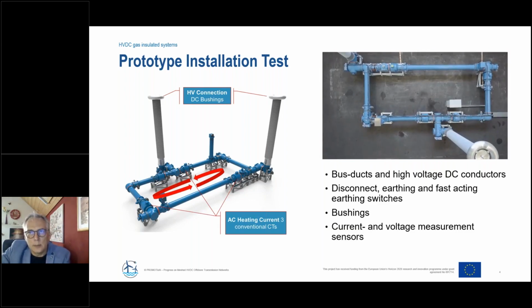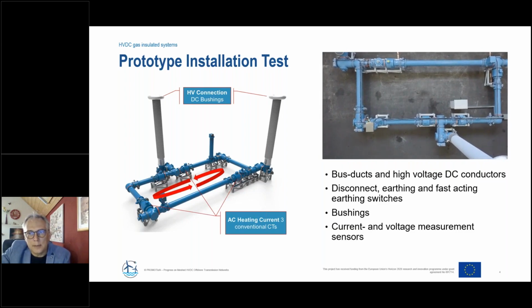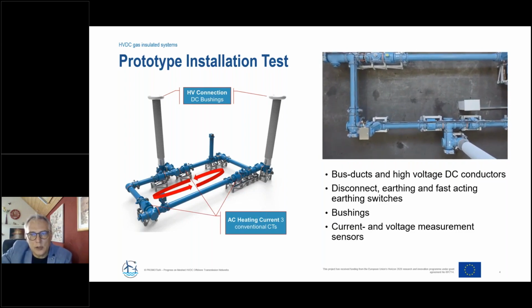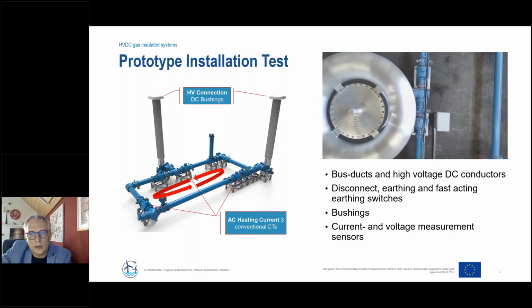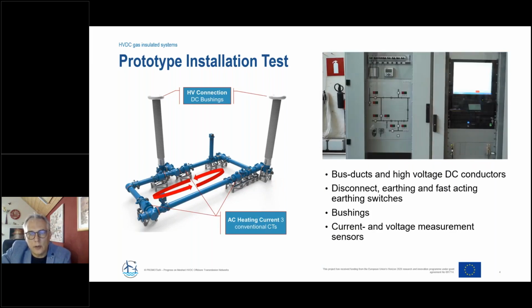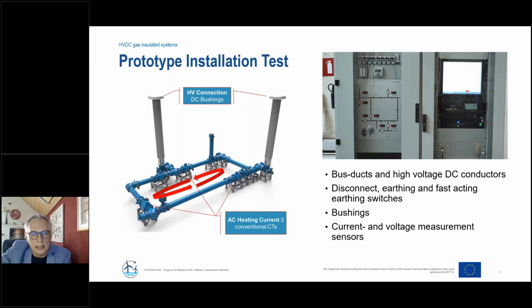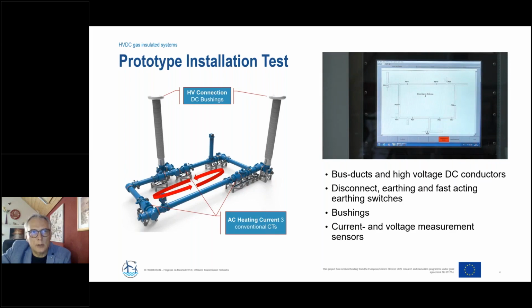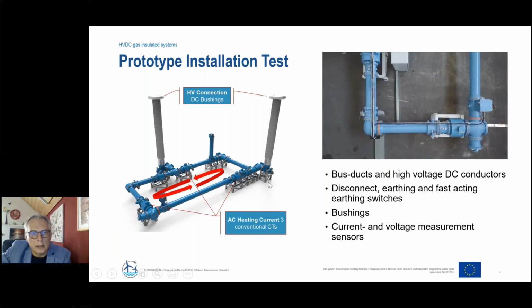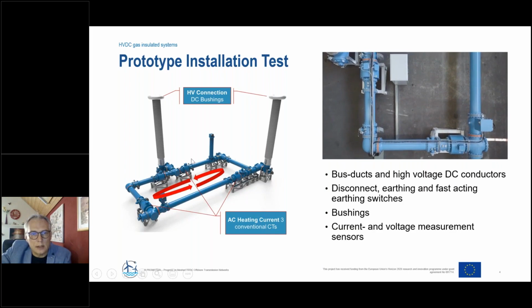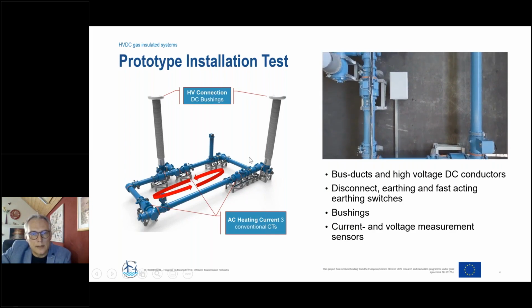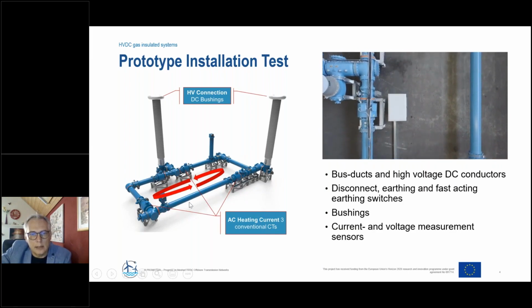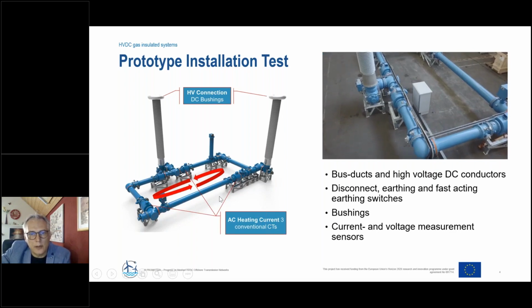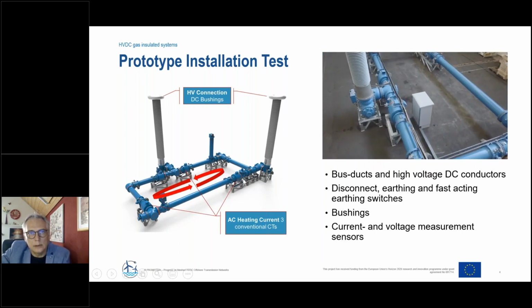To keep in mind the long-time experience, we have increased the test voltage by 20%. So the test voltage for this long-term test was 420 kV. Moreover, we have injected the current, as you can see here, using conventional AC current transformers. So we had at the same time also an AC current of up to 4,000 amps running in the test pole.